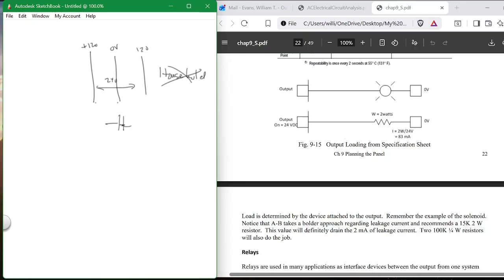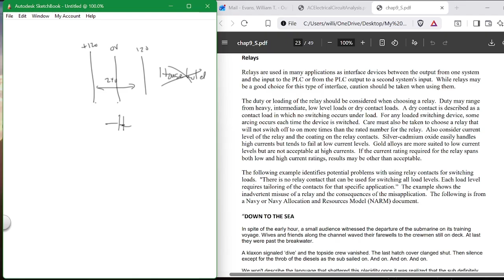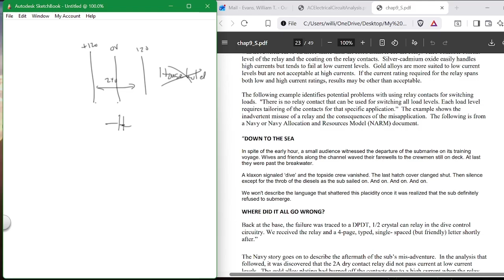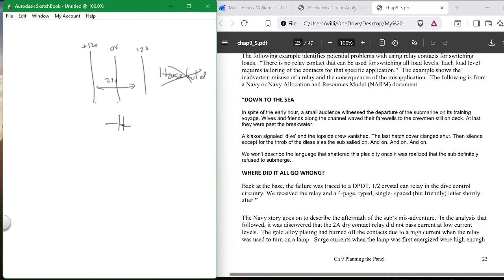Relays are something that you probably will, now that you know how to use them, you'll probably think, oh, that's nice. Relays are really nice. They're not nice. They have a limited number of operations, like 1,000,000 operations, which you say, well, it'll never happen. It does. And also, when they fail, they can fail at the most difficult times, and they're not as reliable as solid state. So if you were to pick a relay, what type of relay would you pick? I will always try to pick a solid state relay over a mechanical contact relay. Even though now that you know about relays, you think, well, I like them because I can see that little thing going on inside of them, and I understand them. Don't be infatuated with relays, okay? Do not use them unless you absolutely have to.